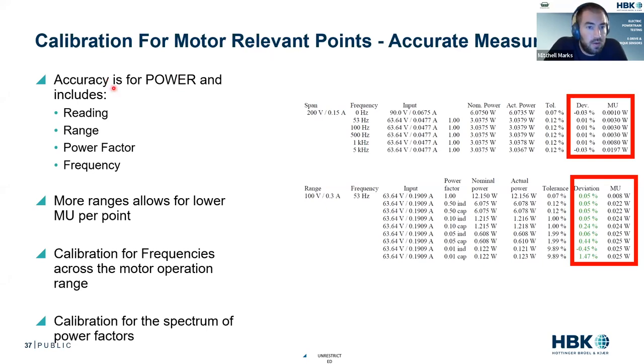So accuracy or measurement uncertainty for power includes the reading of the measurement, the range of the measurement, the power factor, and the fundamental frequency. And one of the cool things that we do at HBK is that we calibrate across different frequencies. We calibrate up to 5 kilohertz fundamental. This allows us to do calibration for those motor specific points. You know, 500 hertz is not unreasonable. 1 kilohertz is not unreasonable. We calibrate at these levels. We try to let you understand your uncertainty at these levels.